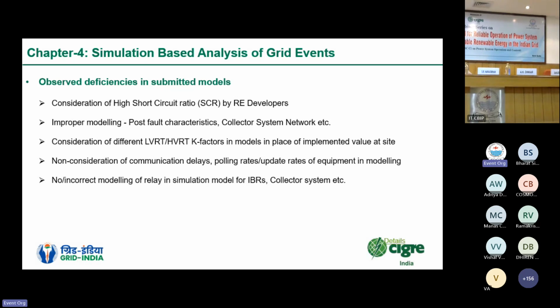So again, the same issue: the K factors placed in the models and the K factors implemented at site were different, which was one finding. And again, in the models, the communication delays, the polling rate of inverters, and update rates of equipment were not considered. So the actual performance was not matching the simulated one. So these were the major issues, the deficiencies identified in the submitted plant models.